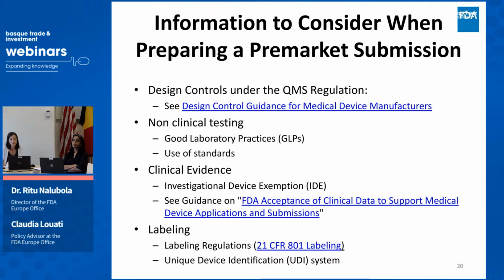Just to close on this, some information to consider when preparing a pre-market submission. One thing that I did not touch upon when I was talking about the pre-market approval, and that I can mention now, is related to inspections, because we did have some questions on inspections. A pre-approval inspection as part of a PMA application is performed to assess the manufacturer's ability to design and manufacture the device in accordance with the conditions specified in the PMA application and the requirements of the quality system regulation. Those pre-approval inspections would normally only be foreseen for PMA applications. There is no requirement, at least for pre-approval inspection, for a 510K.